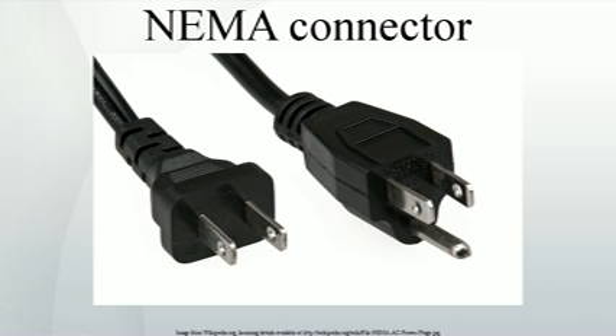Tamper-resistant receptacles. Starting with the 2008 National Electrical Code and the 2009 Canadian Electrical Code, listed tamper-resistant receptacles that address electric shock hazards to children must now be installed in almost all areas of new or renovated dwellings. According to statistics cited by the NFPA, the code change adds only $40 to the cost of building an average, 75 receptacle home in the U.S., yet prevents shock hazards to a child that sticks a single, metal object into the receptacle.